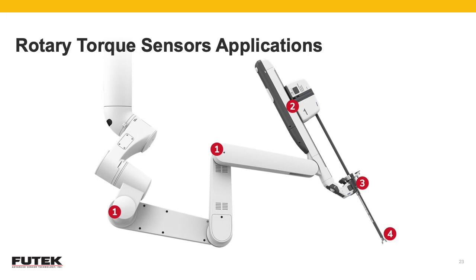Micro rotary torque sensors can be used right between the robot arm and the motor that engages the instrument for control, as they rotate, pull, or push to trigger different functions at the tip of the instrument. Those movements can be monitored with torque feedback. In addition, they can log the torque measurement for post-analysis to see how the arm or its tools can be improved in design for this application.